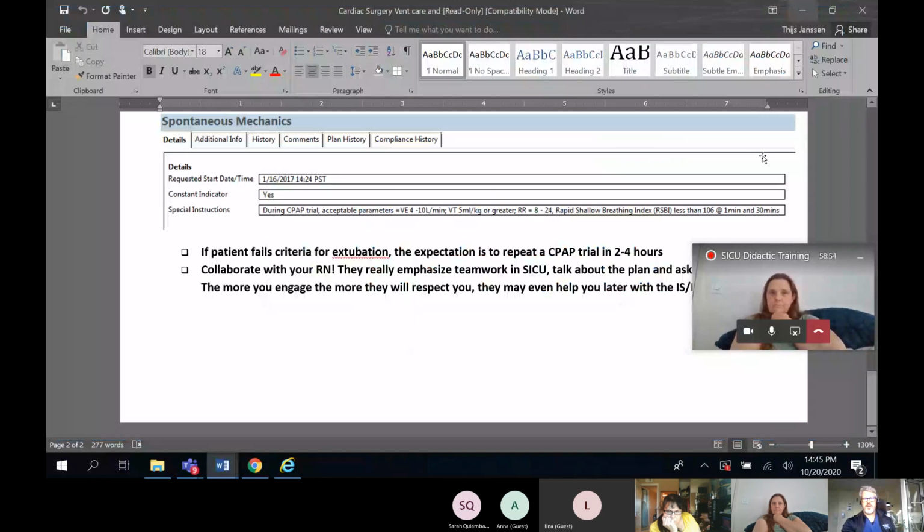So before we go into questions on this, there's a couple things you should know. What you saw was the initial setup. So you'll do initial setup not when the patient is coming from the OR, because they will have been using the setup in the OR already. They'll come out bagging the patient off the INO machine. So they will have done all of those steps except for putting the injector in line and the sample line in line with your vent circuit. Everything will already have been done.